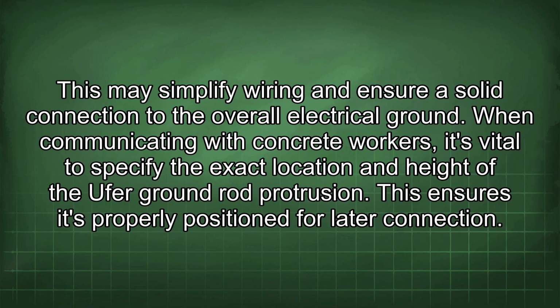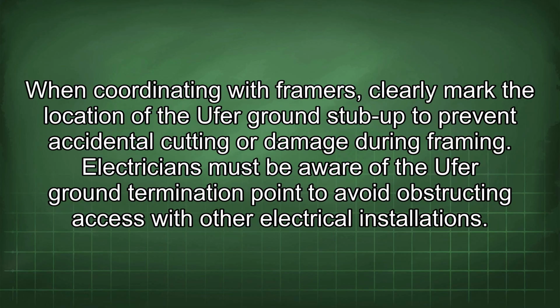When communicating with concrete workers, it's vital to specify the exact location and height of the Ufer ground rod protrusion. This ensures it's properly positioned for later connection. When coordinating with framers, clearly mark the location of the Ufer ground stub-up to prevent accidental cutting or damage during framing. Electricians must be aware of the Ufer ground termination point to avoid obstructing access with other electrical installations.